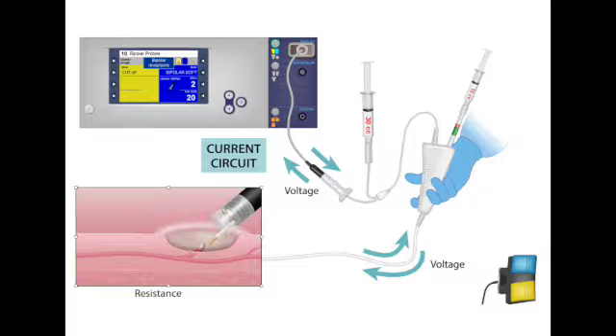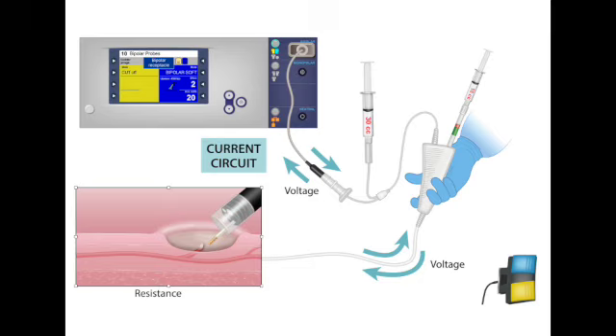Immediately, yeah. Okay, so this often happens in an emergency, right? Things are probably a bit chaotic. What's the holdup in getting this thing ready? It's not just sliding it down the scope, is it? No, definitely not. You've got to get the electrosurgery unit, that ESU, set up and switched on first. That takes a moment. Then you have to specifically select the bipolar program on that machine, and then, of course, hook the probe itself into the correct bipolar outlet.